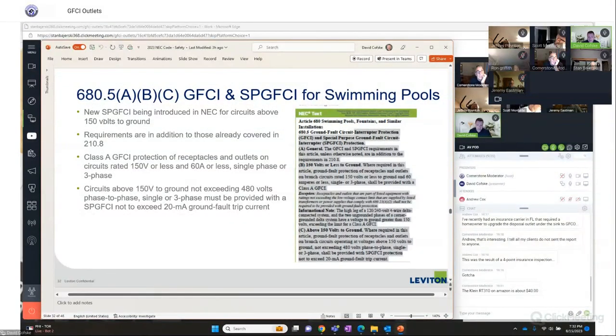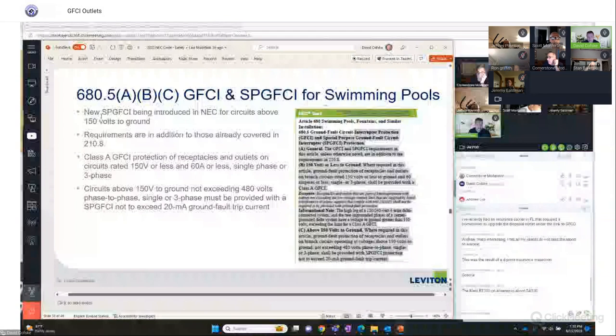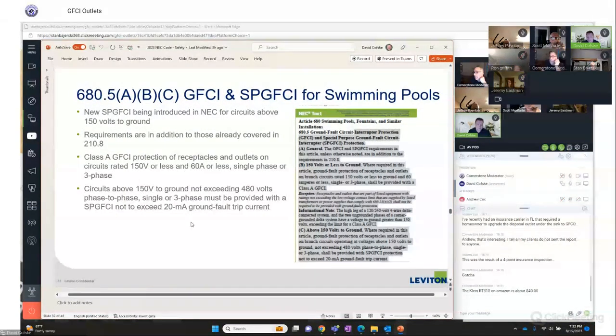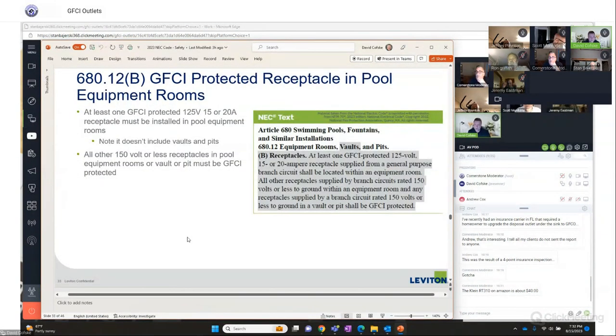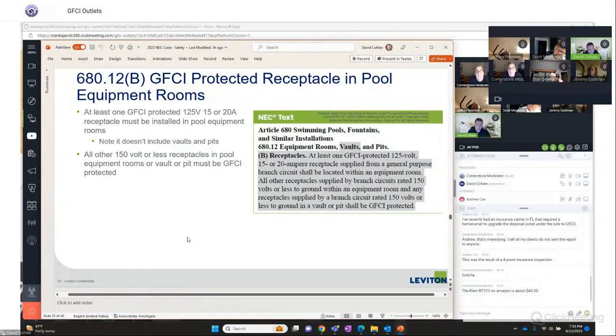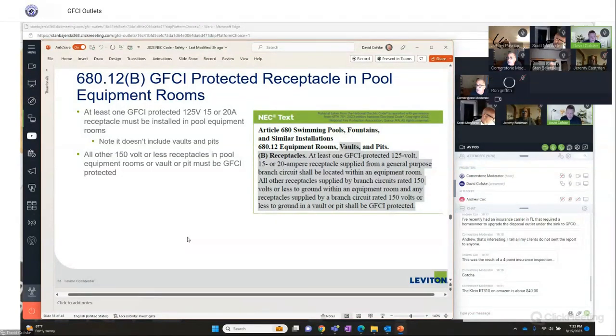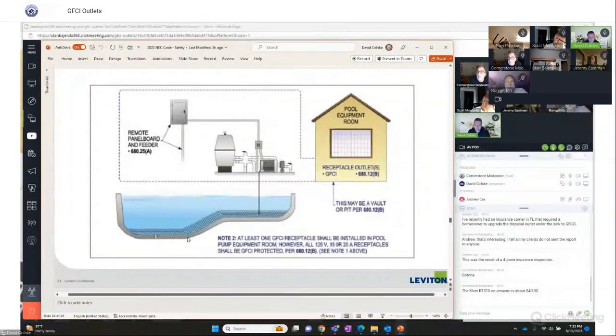And back in the beginning, when we were talking about GFCIs, I talked about UL 943A devices at 5 milliamps. A special purpose GFCI doesn't need to be at 5. It can be at 20 milliamp. And they basically call that a UL 943C device for special purpose GFCI. But again, the code and the requirements, they're not stopping. They're just growing. And this talks about if you have a shed or some type of a dressing room at a pool, it's required to have GFCI protection in that building as such.